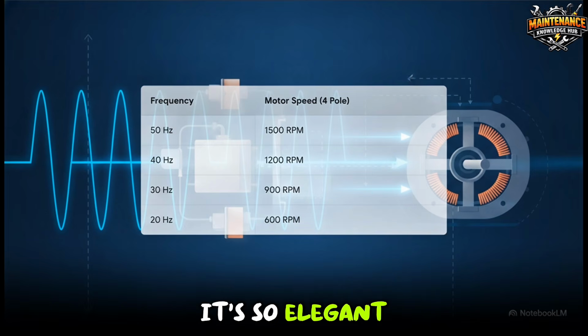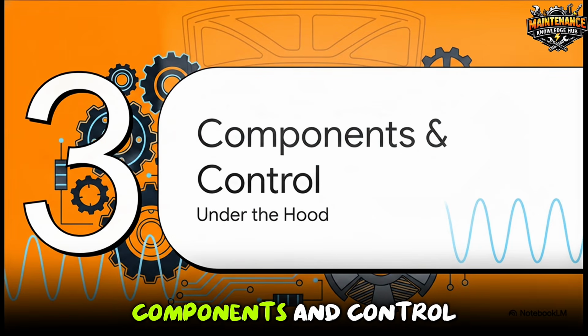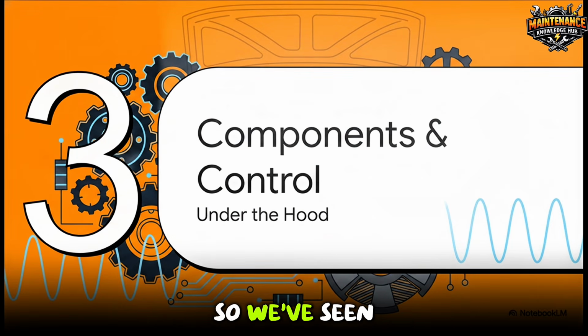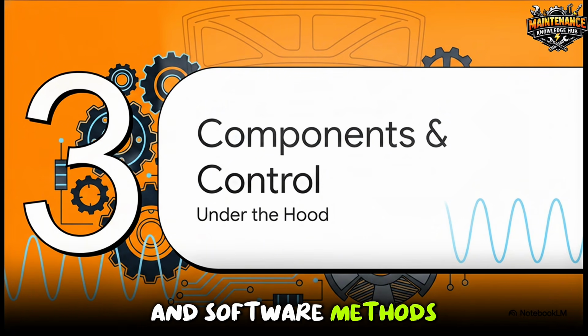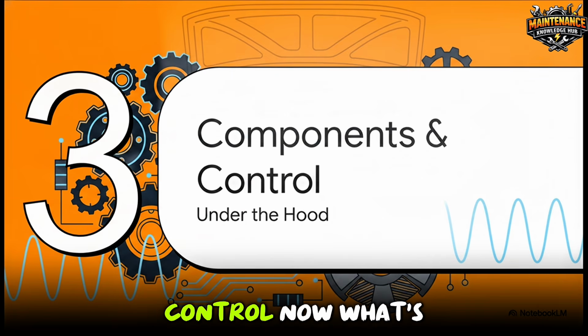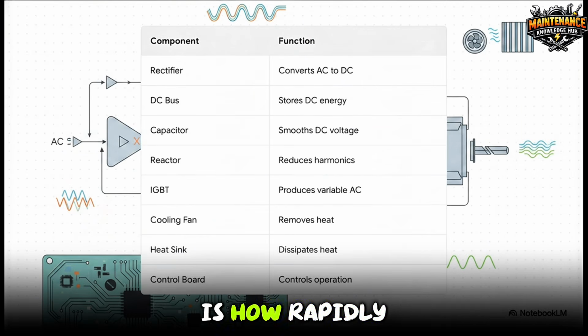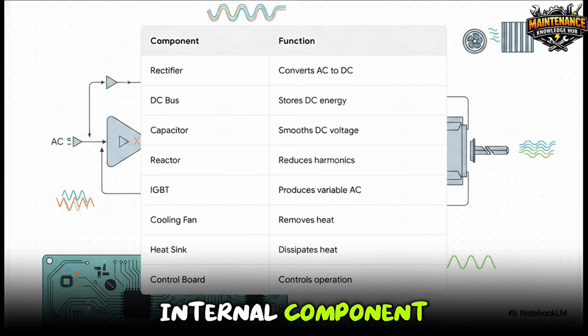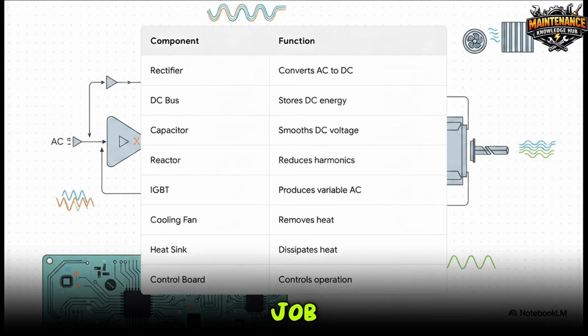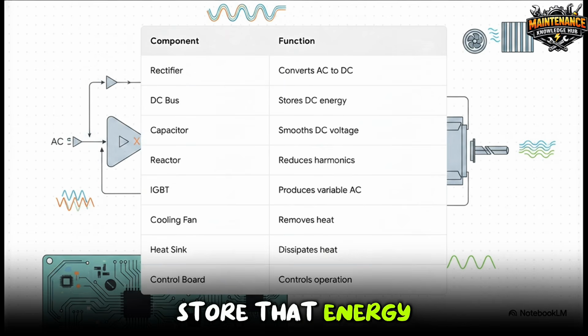It's so elegant. Section 3, components and control. So we've seen the overall flow, but now let's pop the hood and look at the exact hardware components and software methods that give us this incredible control. Now, what's really interesting here is how rapidly we can pair each internal component with its exact job. The rectifier converts AC to DC. Then the DC bus and its capacitors store that energy and smooth the voltage. From there, the IGBT produces that variable AC for the motor.